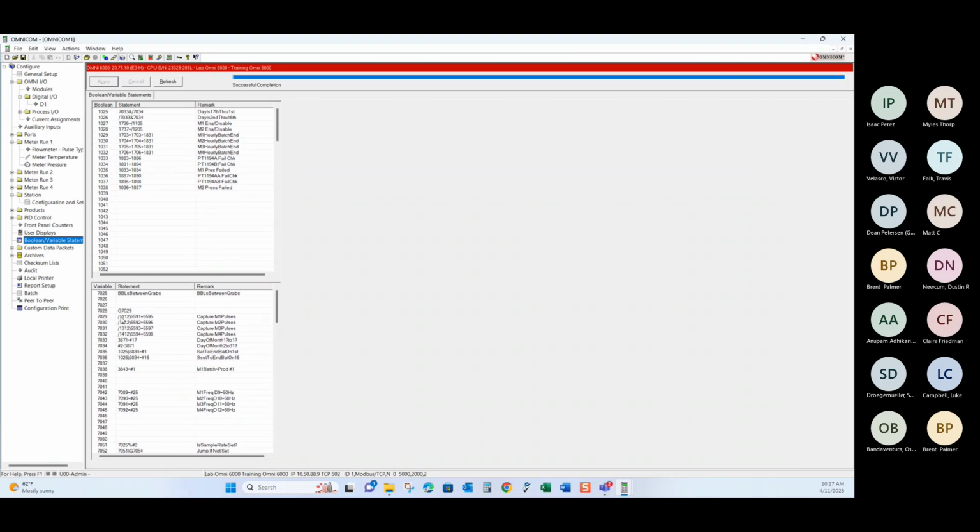If it was in any other position in that statement, that operator would mean divide by, but since it's the very first symbol in there, the Omni knows you're checking to see that 1112 is not true. So in this case, if, which is the close parentheses there, I know it's hard to see, it's kind of small, but if 1112 is not true, and remember 1112, that was the batch in flag acknowledge for meter 1.